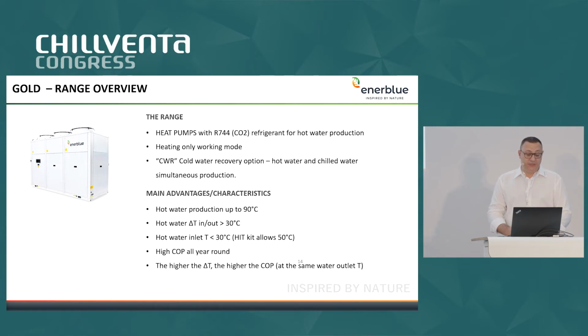Main advantages and characteristics. As I said to you, up to 90 Celsius leaving water temperature. Delta T in this case must be higher than 30 degrees. The hot water inlet temperature maximum is 30 degrees, but we have also an optional kit that allows the unit to work with entering water temperature up to 50 degrees. In any case, for all year round, we can grant high COP for hot water production. And for this specific unit, the higher the delta T, the higher will be the COP for the heating purposes.